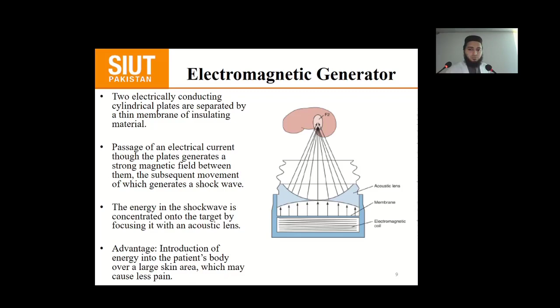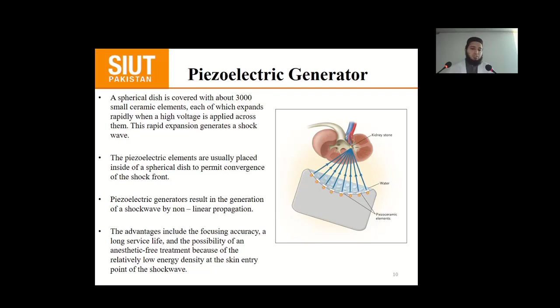In the piezoelectric generator, there is a spherical dish covered with about 3000 small ceramic elements, each of which expands rapidly when a high voltage is applied across them. This rapid expansion generates a shock wave. The piezoelectric elements are usually placed inside a spherical dish to permit convergence of the shock front. Piezoelectric generators generate shock waves by non-linear propagation. The advantages include focusing accuracy, a long service life, and the possibility of anesthetic-free treatment because of the relatively low energy density at the skin entry point of the shock wave.